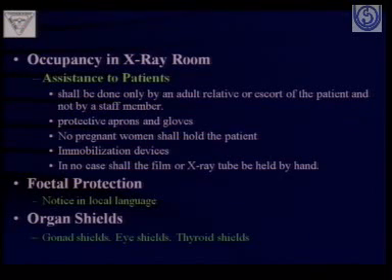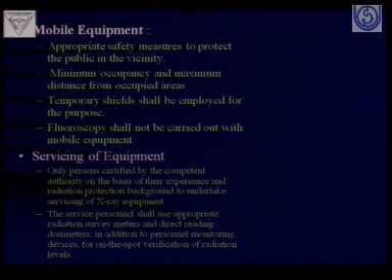And then occupancy in the X-ray room has to be seen. Assistance to the patient should be minimal. Actually, no pregnant women should be holding the patient. Again, there has to be a barrier in between. Fetal protection: notice in the local languages in terms of PNDT, organ shields, gonadal shields, eye shields, thyroid shields. These are very, very important safety requirements nowadays.